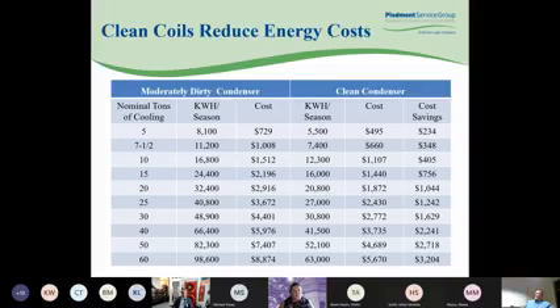There are a lot of variables in coil washing. Time of the year affects it. Too early in the pollen season, you'll have clean coils, and then they'll be recoated as our pollen season shifts. Grass cutters always seem to blow grass up into the condenser coils. The ability to get clean air from around the facility. I've seen facilities that installed their equipment too close to the building and were not able to get enough clean air around the condensing unit, and therefore they weren't able to make cold water.